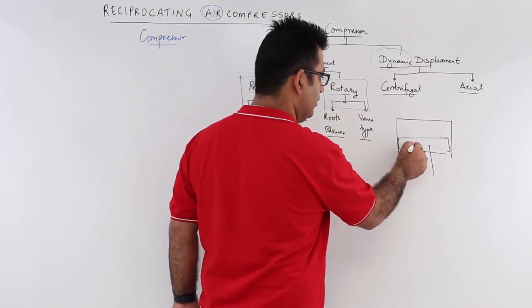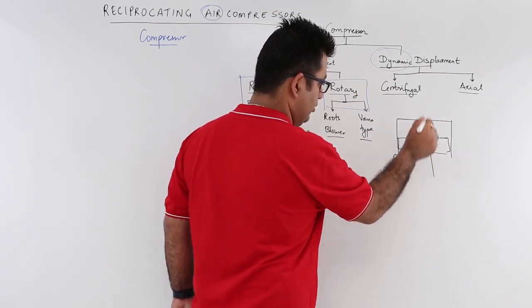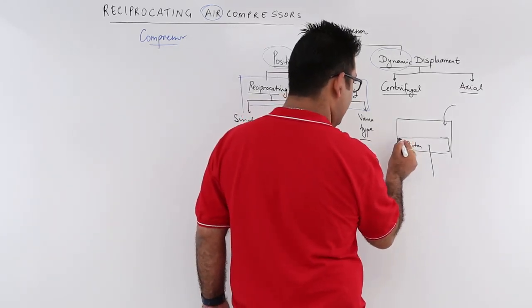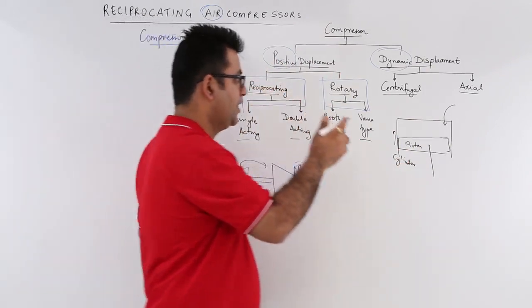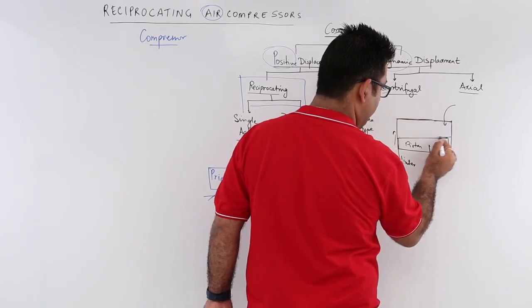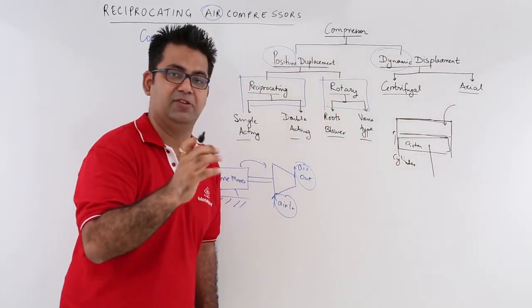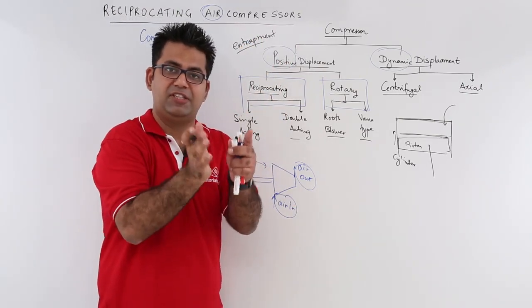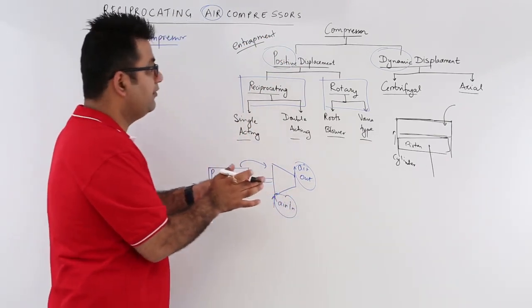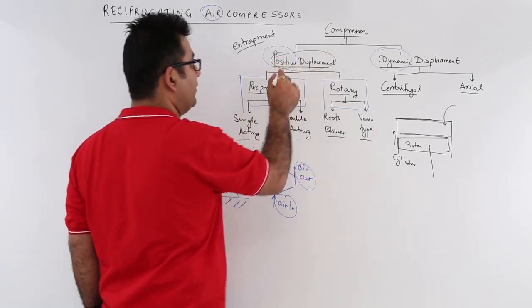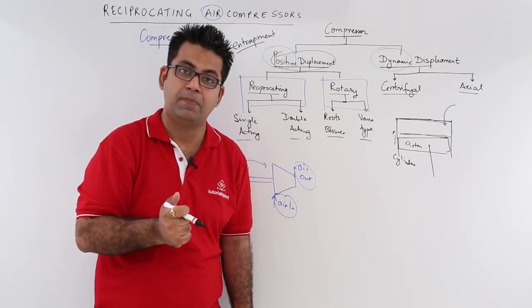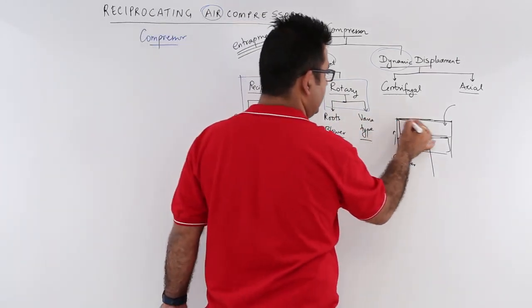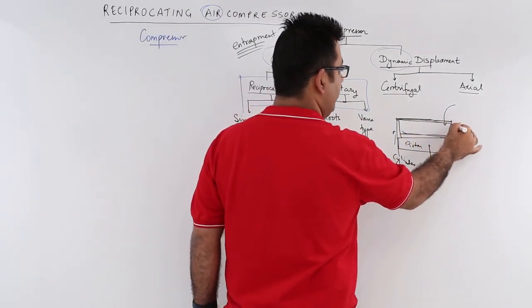This is the piston, and this is the cylinder. When air comes into this chamber, the air is compressed by moving the piston vertically upwards. You are basically compressing the air against a fixed boundary — you are entrapping the air. The word is entrapment. When the working fluid is entrapped into a fixed volume which is further compressed, in simple language a positive displacement compressor traps the working fluid in a fixed region and then increases the pressure from P1 to P2.